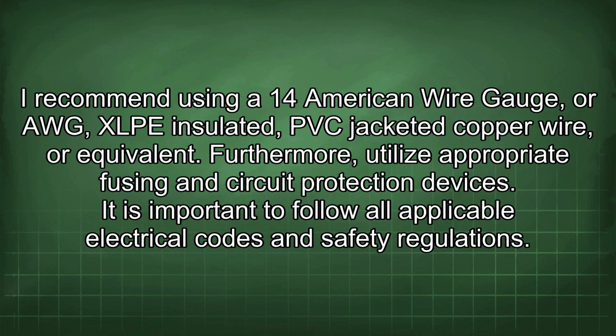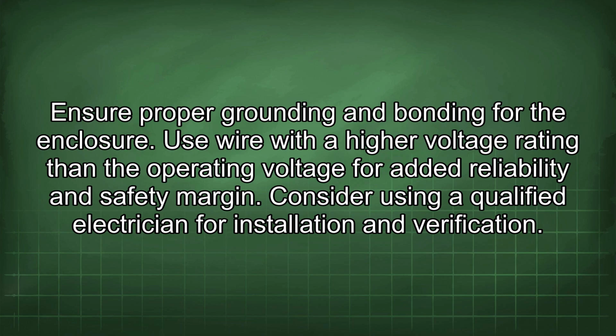I recommend using a 14 American wire gauge, or AWG, XLPE insulated, PVC jacketed copper wire, or equivalent. Furthermore, utilize appropriate fusing and circuit protection devices. It is important to follow all applicable electrical codes and safety regulations. Ensure proper grounding and bonding for the enclosure. Use wire with a higher voltage rating than the operating voltage for added reliability and safety margin. Consider using a qualified electrician for installation and verification.